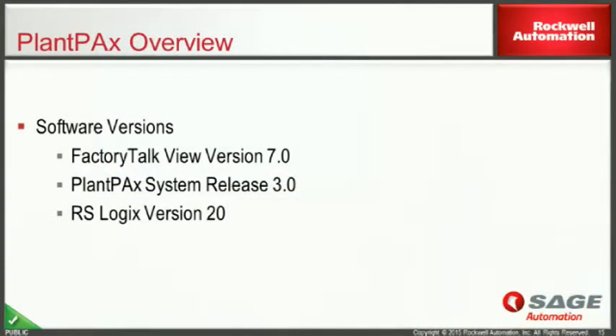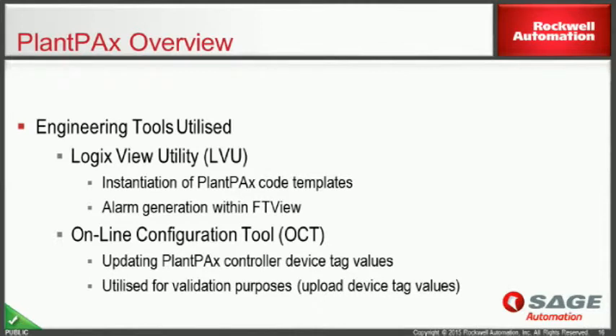PlantPAx Overview, software versions, we used FactoryTalk View version 7, PlantPAx System Release 3, and RS Logix version 20. The engineering tools that we've utilised is Logix View Utility, LVU, for instantiation of all PlantPAx code templates within the controller, and the alarm generation within FactoryTalk View. LVU is a hell of a lot more capable, but due to some of the customisation that we needed to implement, driven by customer requirements, we weren't able to use LVU fully.